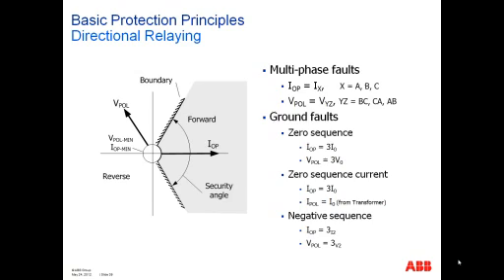Here are some basic protection principles. You have a reference quantity and an operating quantity, and you have a boundary condition such that for multi-phase faults, we show you some quantities where the operating quantity would be the phase current IX, where X is equal to A, B, or C, and the polarizing quantity would be the voltage that is in quadrature to the operating current, or let's say the current you're measuring when there's no fault. It would be the voltage that is in quadrature to that, or what they call cross phase. In other words, if you're looking at IA at unity power factor, then you would be using voltage VBC.